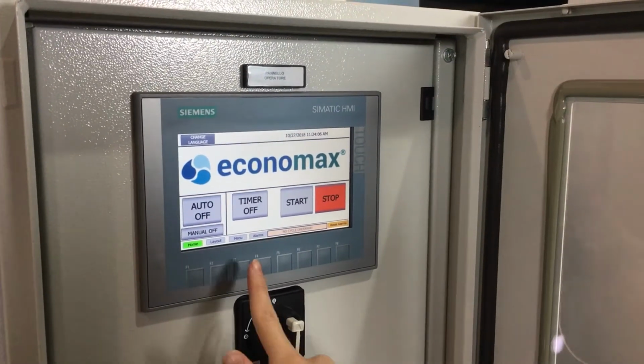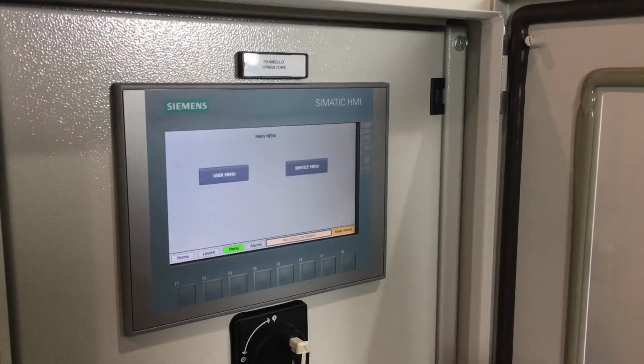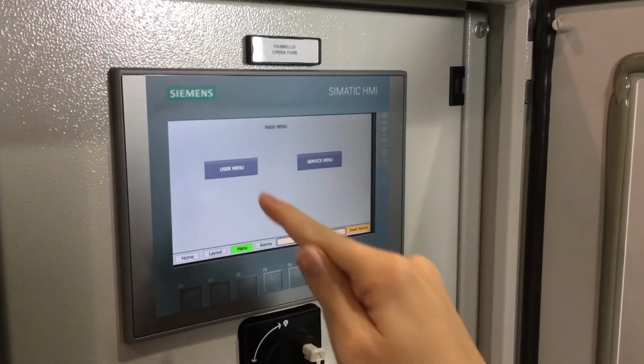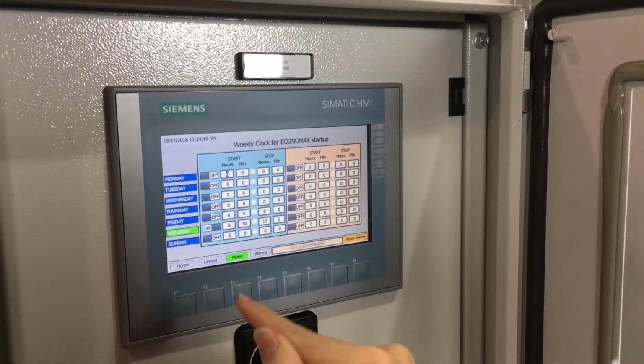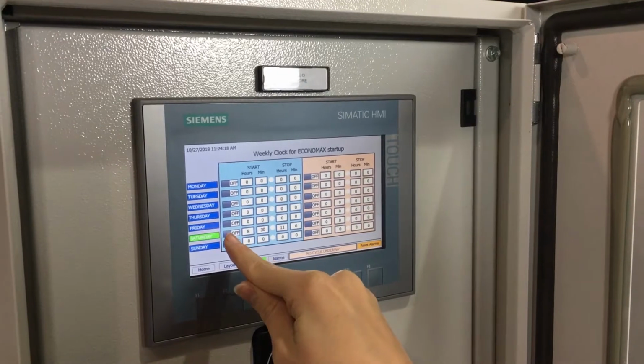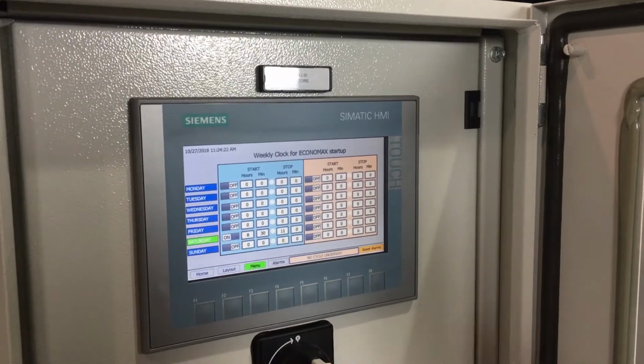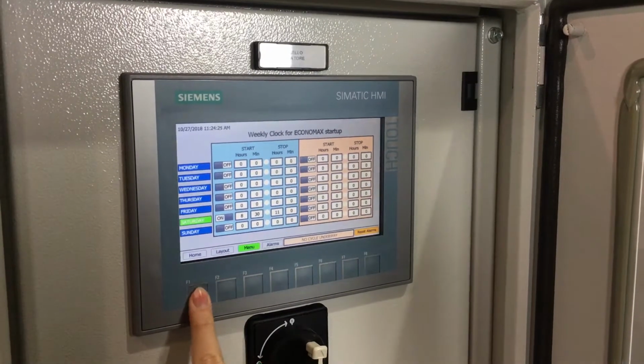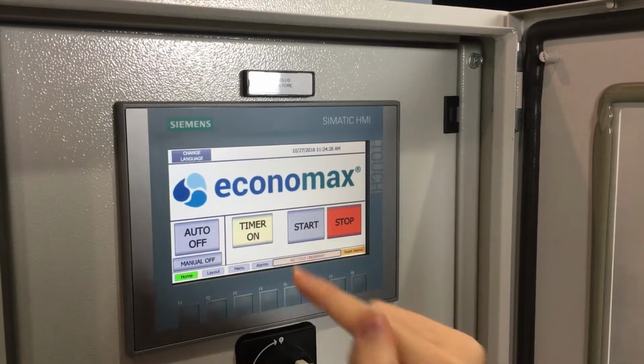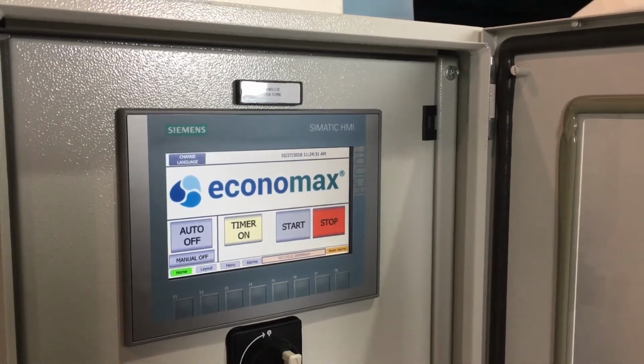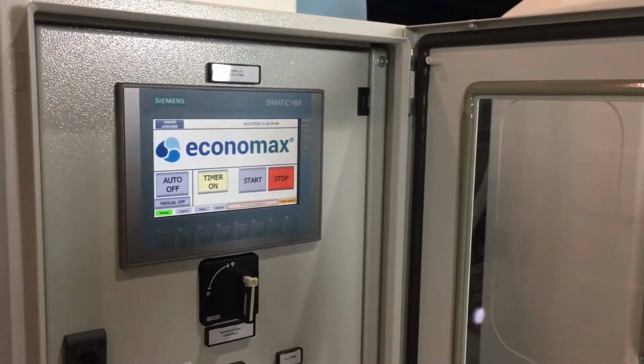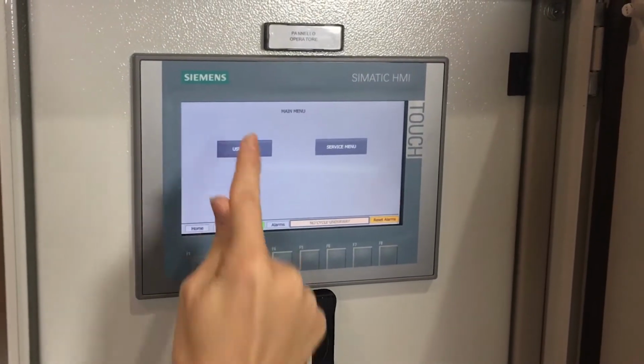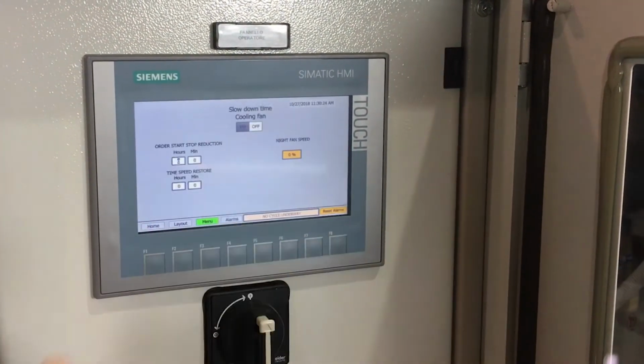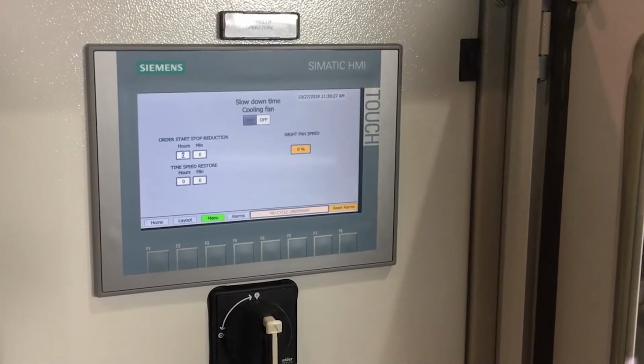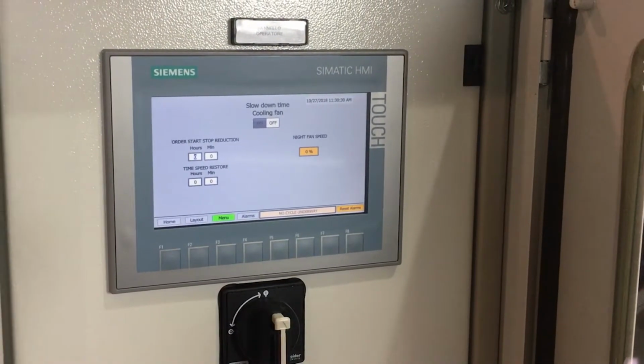Timer mode. Push the F3 button to access the machine settings. From here, under User menu and Weekly Clock Ignition, you can easily select the days and the times that you would like the machine to operate. To go back to the Home menu, press F1. Now press Timer and then Start. The tower is now in timer mode and will work at the set time. Through the menu screen, you can also set the parameters for different functions, including cleaning and maintenance date and indicating the times to reduce the maximum rotation speed of the fan to further reduce noise emissions during the night.